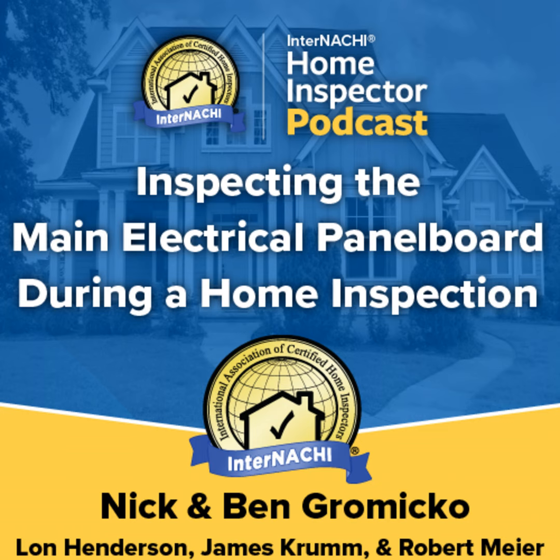Other issues with these panels are that breakers can fatigue over time, become loose on their buses, lose connection, overheat, and even melt. Most, if not all, aftermarket replacement breakers are not UL approved and cannot be considered reliable. Some aftermarket breakers are incompatible despite their advertising, such as aftermarket Pushmatic breakers. Using other branded breakers that may fit the buses is not an approved repair or considered safe.